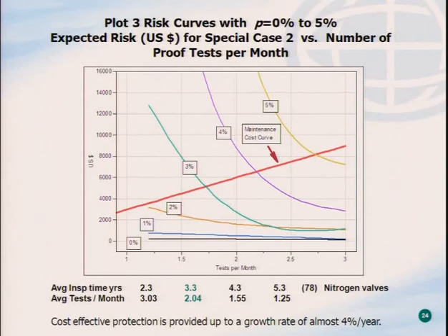So where we were last year, we analyzed a lot of the data, the inspection data, that we have, and we used the maintenance interval. Or folks in the past used the maintenance interval as the time to failure. And what we found last year in simulations that I ran was we could be underestimating the risk by a factor up to 100%. And because of that, we started looking at ways that we could evaluate performance of valves without knowing the actual failure date.